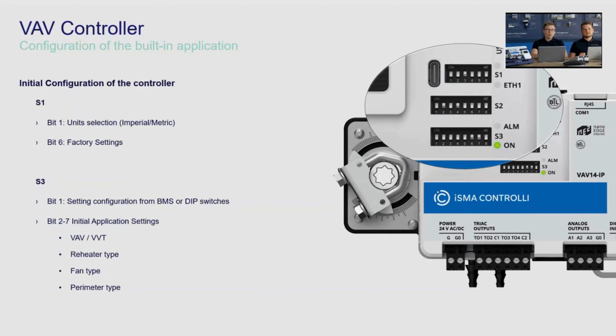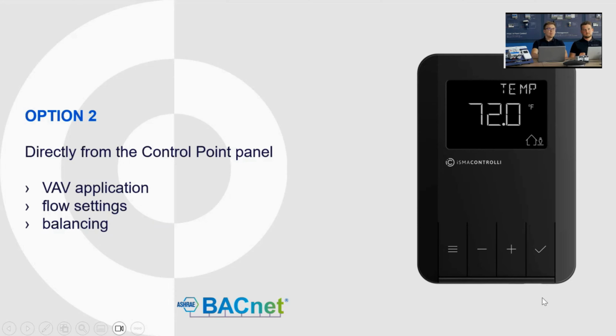What is very important is that together with the second option and the CP-VAV panel, we can use the space sensor, the temperature sensor, CO2 sensor, humidity sensor, and use them in the application. It works out of the box. Okay, great. So maybe let's look at how the configuration option number 2 would look. So we have the control point panel from which we can configure the VAV application. We can set up the flow and do the balancing for one single unit.